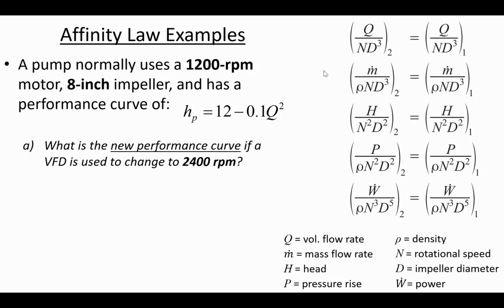But that's at a flow rate of zero. The faster the flow rate moves, the less pump head it adds. So it can add a lot of pressure at low flow rate, or a little pressure at higher flow rate. That's how pump performance curves operate: you have the cutoff head, and the maximum head is reduced based on the flow rate.